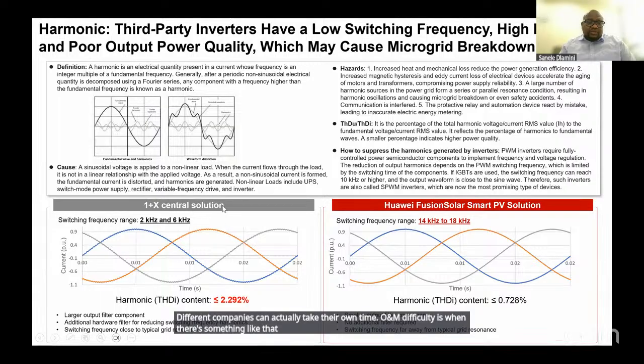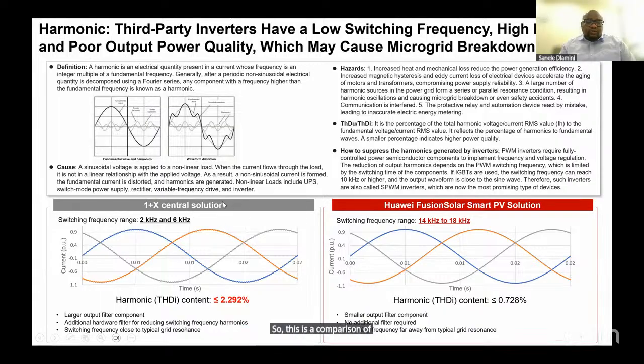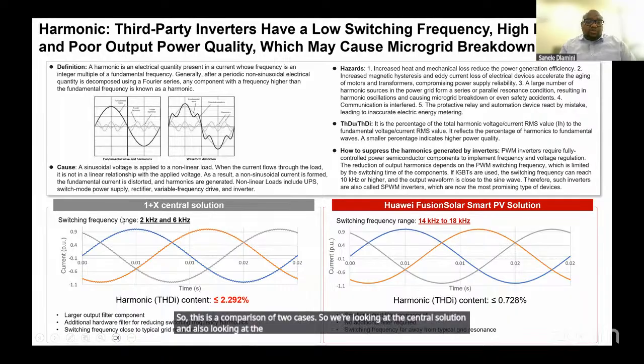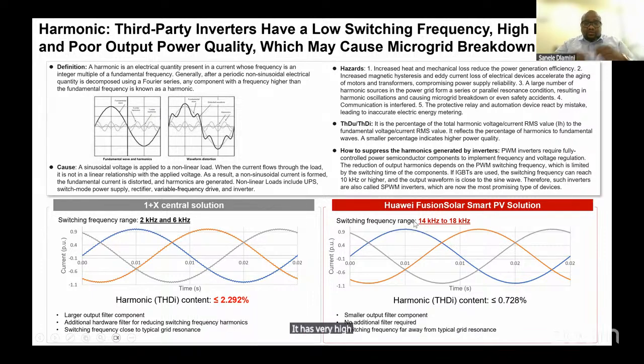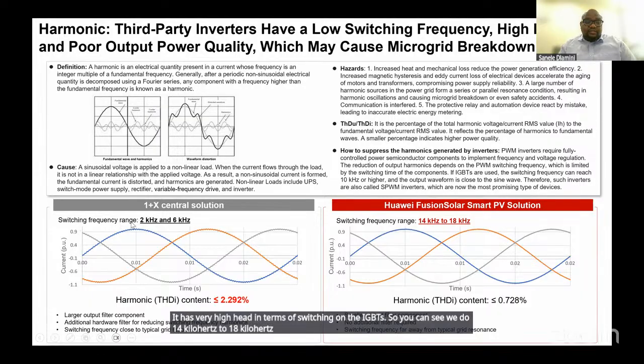So this is a comparison of two cases. We're looking at the central solution and also looking at the string solution. So you'll see that our string solution has very high rates in terms of switching on the IGBTs. You can see we do 14 kilohertz to 18 kilohertz, and the switching frequency range on the central is 2 kilohertz to 6 kilohertz. So you will see those small spikes.